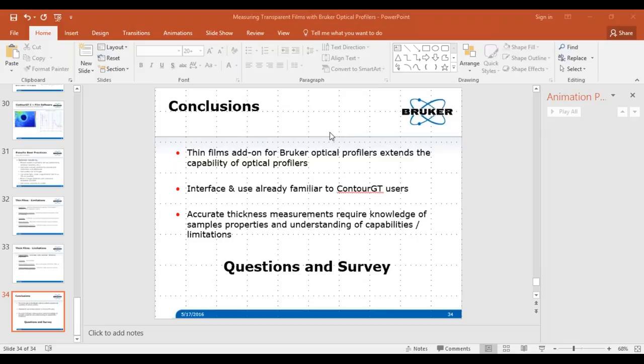Can you measure patterned thin films? Generally, yes — it depends on how thick the film is. Thicker films will be much easier. Above 100 nanometers, 500 nanometers shouldn't be a problem and should certainly be doable. I haven't personally had too much trouble pushing thin film measurements up in magnification. As I mentioned, thick film is a lot more sensitive to magnification. There isn't as strong an effect with thin film measurements.